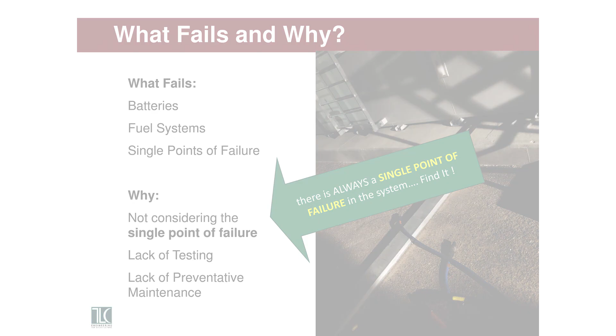Maybe it wasn't set up right in the first place, or maybe we haven't considered single point of failure. In my experience, no matter how much redundancy you try to build into the system, there's almost always a single point of failure that will bring the whole thing down. You've got multiple generators, redundancy, and paralleling gear, and then there's a single pump in the main tank of the fuel system that craps out, something like that. So we're always looking for those single points of failure, both in the design phase and in the construction and acceptance testing phase as well.